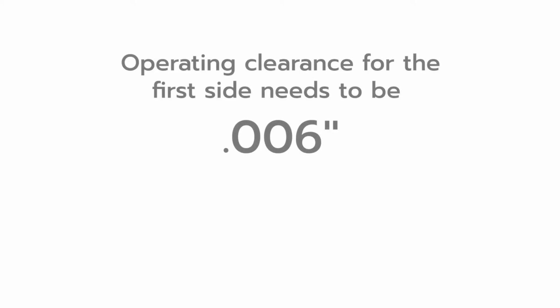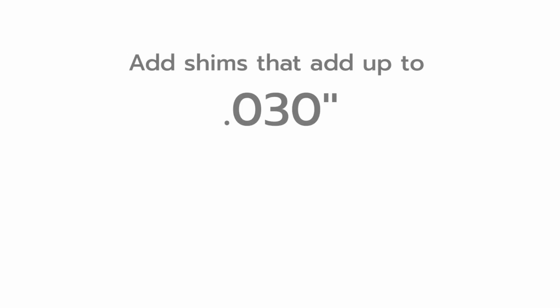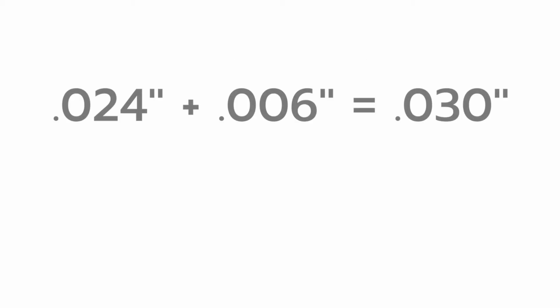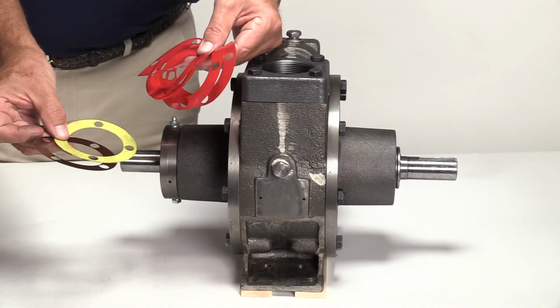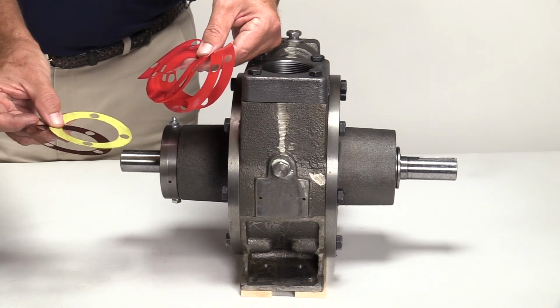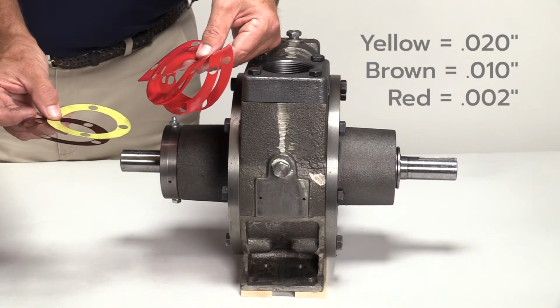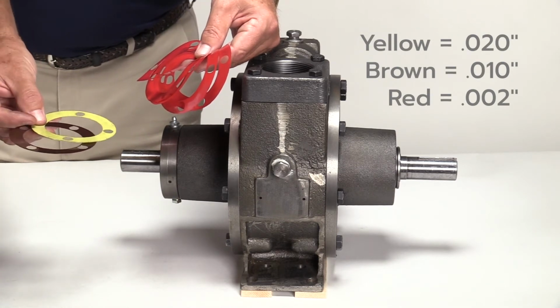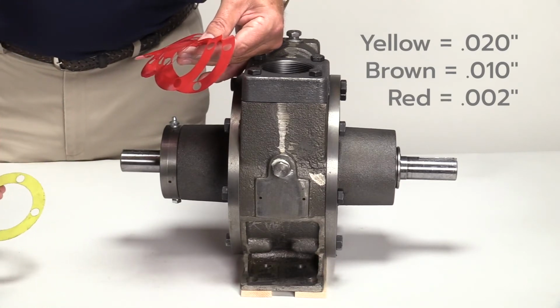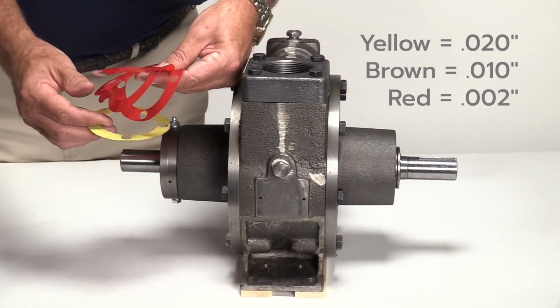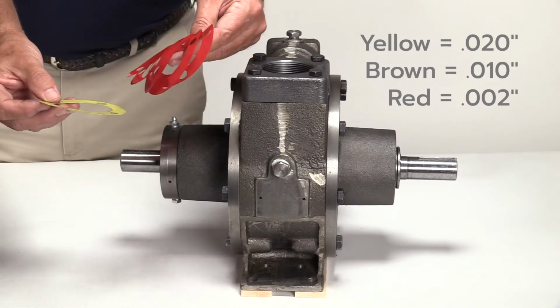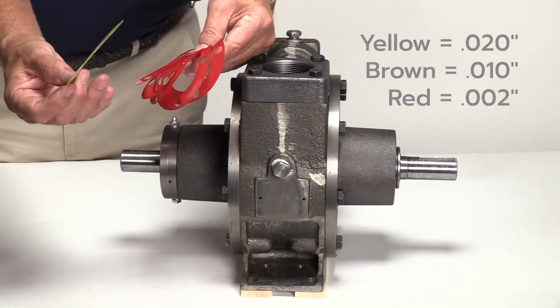The operating clearance for the first side needs to be 6 thousandths. To establish the operating clearance of 6 thousandths, add shims that bring the total amount of clearance between the bearing cap and the pump head to 30 thousandths. 24 thousandths baseline clearance plus 6 thousandths equals 30 thousandths worth of shims that need to be added. Shim the pump using a combination of shims totaling 30 thousandths. For example, you could use one yellow 20 thousandths shim and one brown 10 thousandths shim. Or, to allow for finer adjustments in the future, you can use one yellow 20 thousandths shim and 5 red 2 thousandths shims, which still accomplishes 30 thousandths worth of shimming.